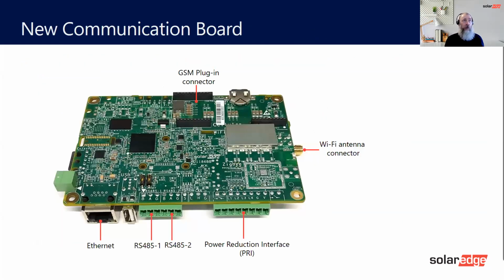This is a communication board here. It's the new one. If you start at the 12 o'clock position here, you can see we have some slots. This is the slot for the GSM, so it allows you to use cellular technology. It's also the slot for a new product which is coming up, a new form of communication that we're working on. We also have on here the communication for home automation or smart energy devices; that would plug in there. This battery here is to keep everything going should there be a power failure or should the inverter be turned off. It's like a memory device, backup memory.